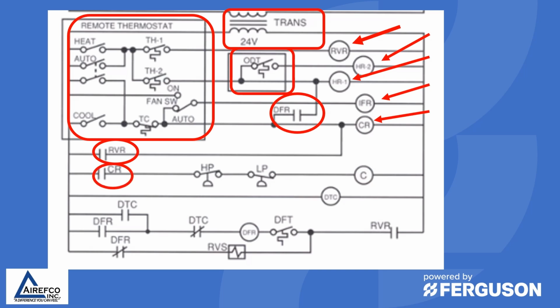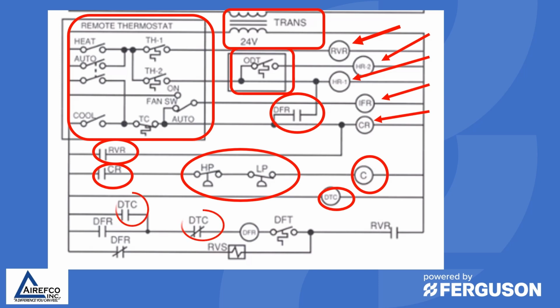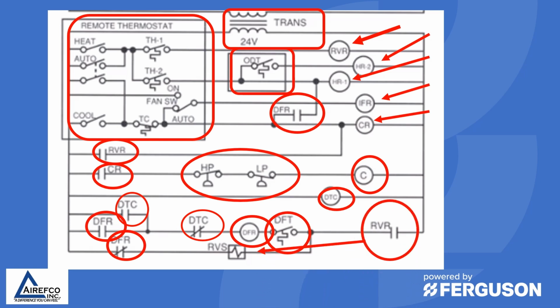You have your control relay that controls the power to the contactor. You have your high pressure and low pressure switches. You have your contactor coil, which is energized when the control relay closes and the high pressure and low pressure switch is closed. We have our defrost timer, as well as the associated open and closed contacts for the defrost timer. We have our DFR, or contacts that are associated with our defrost relay. We have the defrost relay here with a thermostat that will allow the system to go into defrost at a certain temperature. And then we have our reversing valve relay that will energize the reversing valve in the cooling mode to put the heat pump into cooling. It is very important to understand all these different symbols and how they operate on a system, and the wiring diagram will tell us that.